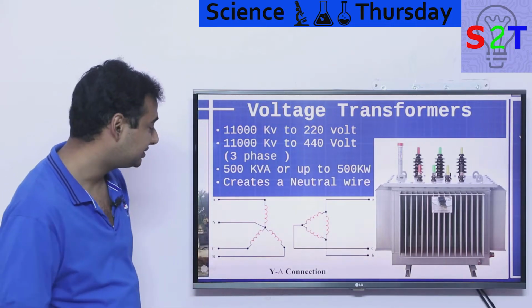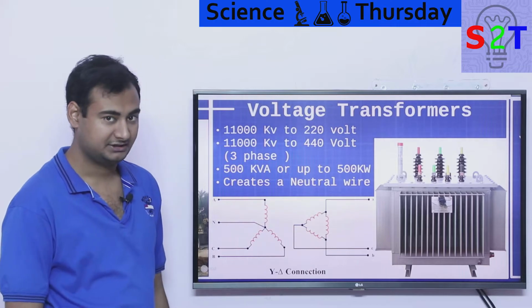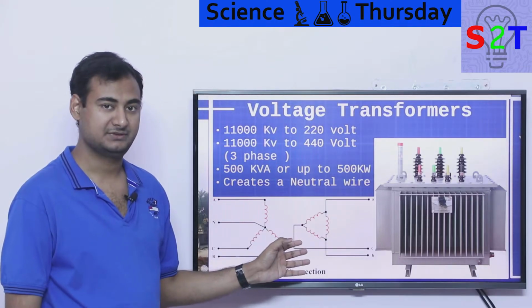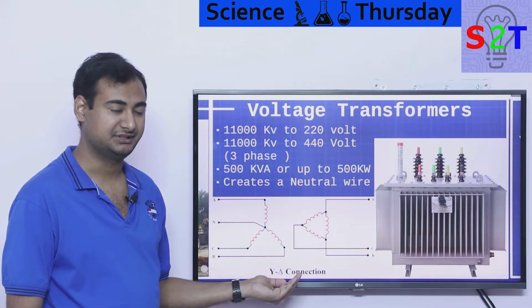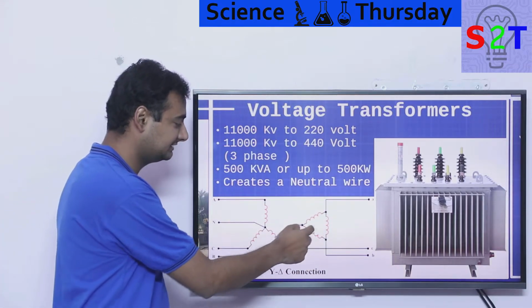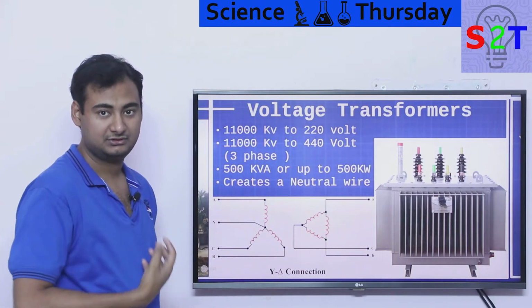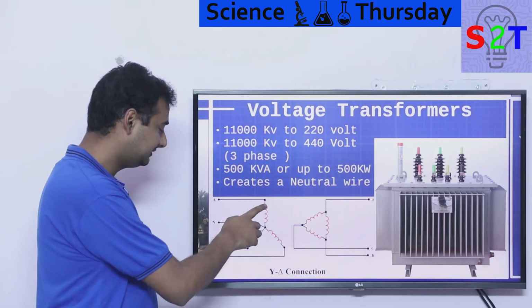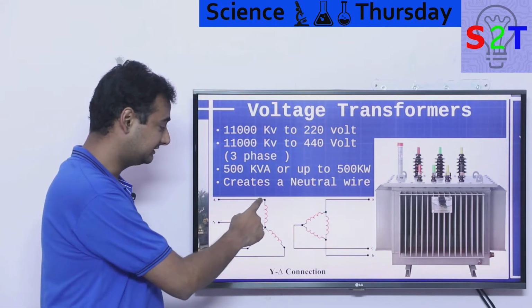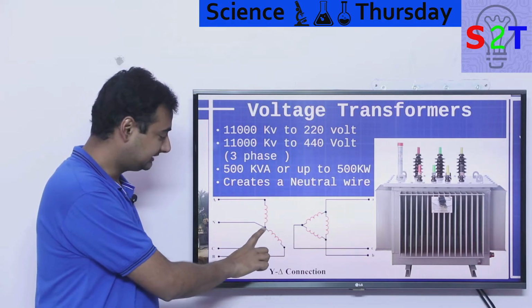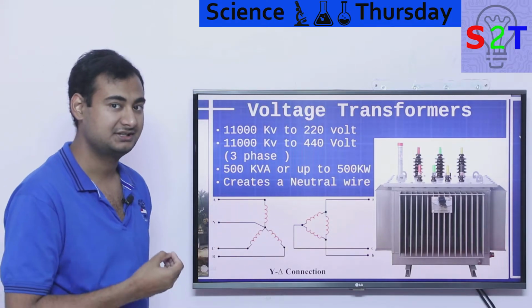Now that is being accomplished by what we call the delta-Y connection. Delta is generally the primary, where your high voltage is coming in. It's connected like a delta, so it only has 3 points. Then on the step-down side, it's converted to what we call a Y configuration. In a Y you can see there are 4 points, and the center point acts as a neutral because the voltage there is 0.